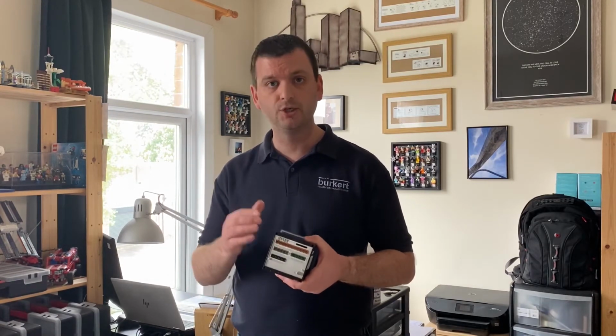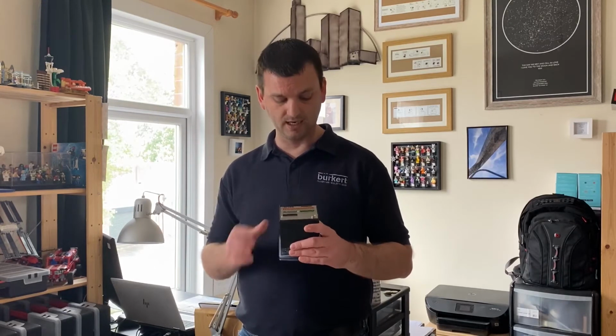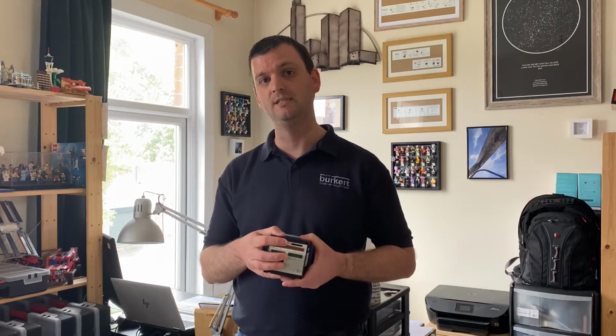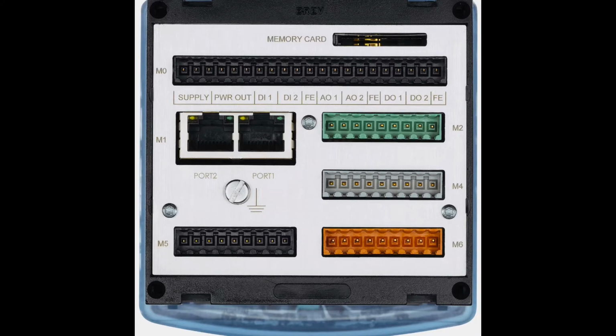The Type 8619 Multicell is capable of handling up to 6 modules within the device, and this allows us to feed in a range of inputs and outputs as the client requires. For example, we can feed pH, ORP, conductivity and chlorine as part of the standard system. We can also include digital inputs from flow sensors as well as analog inputs from level devices and pressure sensors. At the same time, we can extract information out via the digital outputs and the analog outputs, as well as an SD card for data logging purposes. We also move into digital communications platforms, so we can have Ethernet and Profinet as an output from this device as well.